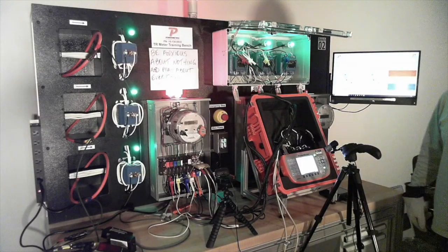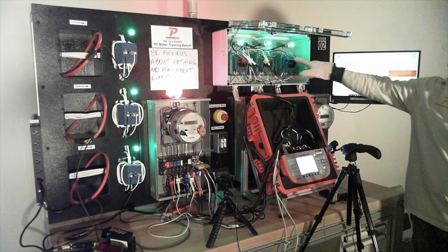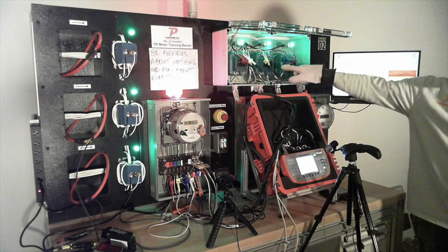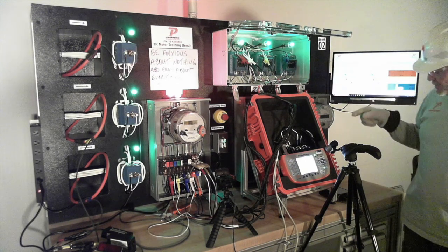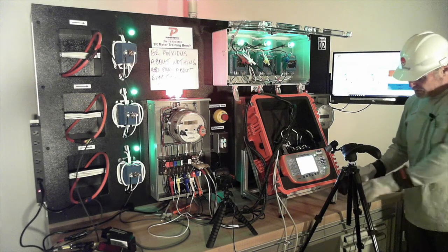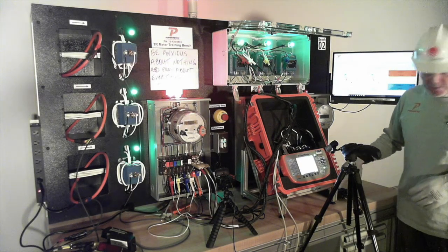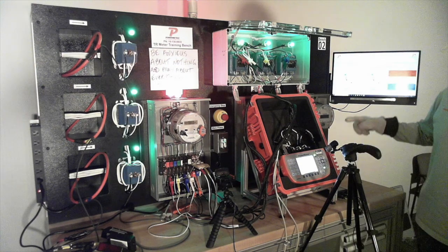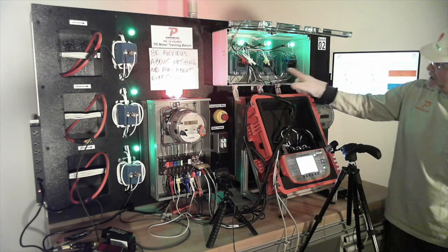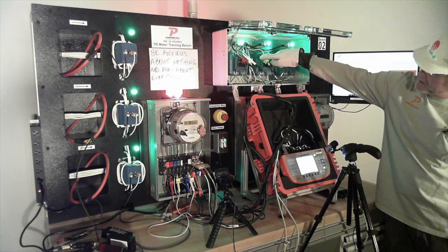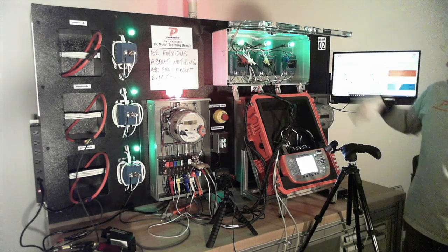I just go where Jarrett points. So I just want to show, you can see our PTs up here, and where we made our connections for our PTs, okay? I came right here, and I'm using our VP600, which is for your lower voltages. We also have, of course, the high voltage probe. This is our lower voltage probe, which we're going to use here. So what I've done is I've connected right here. I've got on my 3 PTs here. All of our returns are tied together, so I've got my white connected here, and then I've got A, B, and C phases, okay?